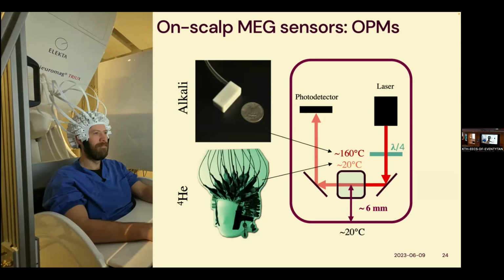So it also has roughly 1 millimeter distance from the outer case, but because it's much bigger, the center of it is also 6 millimeters away. And in this volume, you get an integration. So the signal that you get out is actually an integration over the whole volume, which is why I'm pointing out here the center and not where the cell begins.